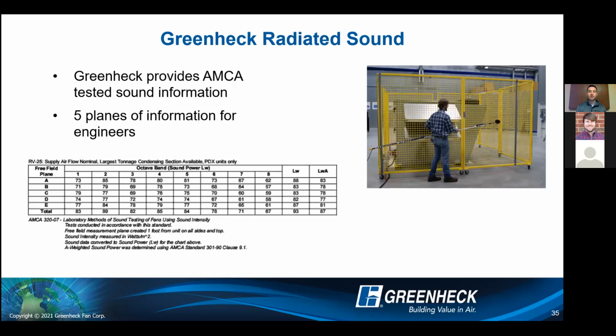Another nice thing is radiated sound. So again, talking about sound ordinances, there's a couple of things I mentioned that we do, like the low sound condenser fans, the base insulation, things like that. But with the radiated sound, we provide AMCA tested sound information in our submittal. So we have 5 planes of information for you guys in the submittal package. You can see in the picture, that's an example of how we test that unit. If you've ever been up to Greenheck, you might have seen our Innovation Center, which is amazing. And what's nice about the Innovation Center is it is built on 1,000 different isolators so that that actual innovation chamber, or that sound chamber, is isolated from the rest of the equipment. So it truly does give us accurate seismic calculations as well as sound ratings that you might see.